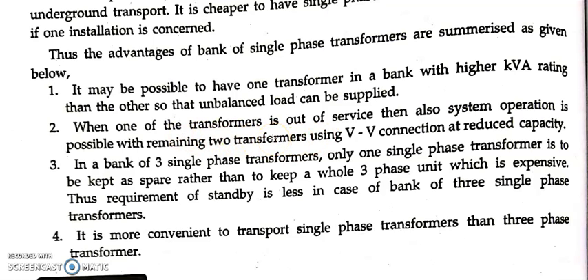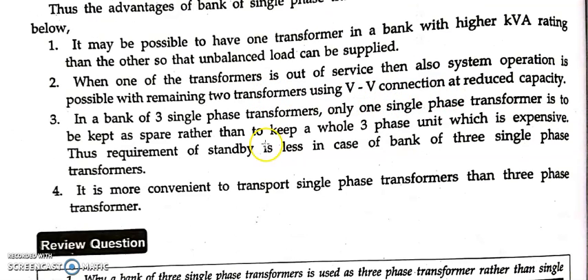Again, like I told you, when one of the transformers is out of service, say one of the transformers is faulty, then you can use two single phase transformers in the form of VV connection. VV connection means what? Open delta connection. Okay, the delta closure is not there, right? So it is called as VV connection at a reduced capacity, meaning the kVA rating will be reduced.